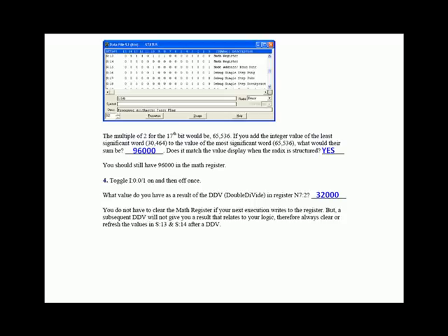Simply an introduction. Always keep in mind that if you select math overflow by setting S:2/14 to 1, then if you do a math function that has a result that goes higher than 32,767, the overflow will go into S14. However, that's still an overflow. All you did was select that you want the overflow to go into S14, but you still have an overflow condition that will fault the processor unless you always include an unlatch S:5/0. In other words, unlatch the overflow trap before the rungs of logic are complete. If you put it as the last rung in your program file, it will always clear that bit so you don't fault the processor. So really, it's all about a manipulation of a few bits and keeping track of what's in S13 and 14. Because remember, you cannot display this 32-bit version of S13 and 14.